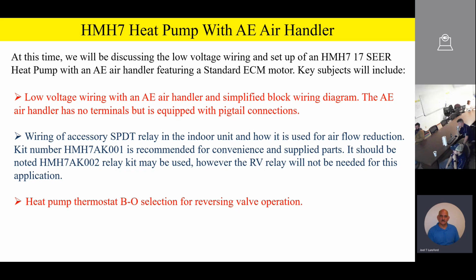Okay. In addition, if you're going to have these set up, you're going to use just a regular heat pump thermostat, but you're going to have to make sure that whatever heat pump thermostat you use, and I want to stress these are just 24-volt thermostats, these are non-communicating standard heat pump thermostats. So whatever your favorite thermostat is, an Aprilaire or a Robertshaw or a Honeywell, your favorite heat pump thermostat is going to be compatible with these products.